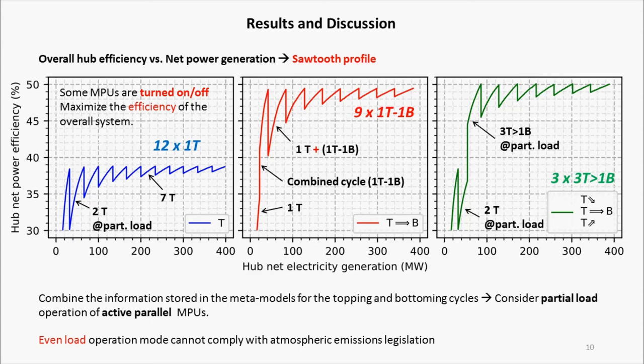It must be also noted that since the power hub configurations have to satisfy both the peak and the lowermost electricity demands of the 4 FPSOs, the operation of a standalone gas turbine system, located either in the power hub or in the productive FPSO, would be necessary. Otherwise, an extreme derating of the combined cycle would not be emission compliant. It can be also seen that the main difference between the two sawtooth plots, based on combined cycles, the red and the green plots, lies on the scale of the bottoming cycle installed.